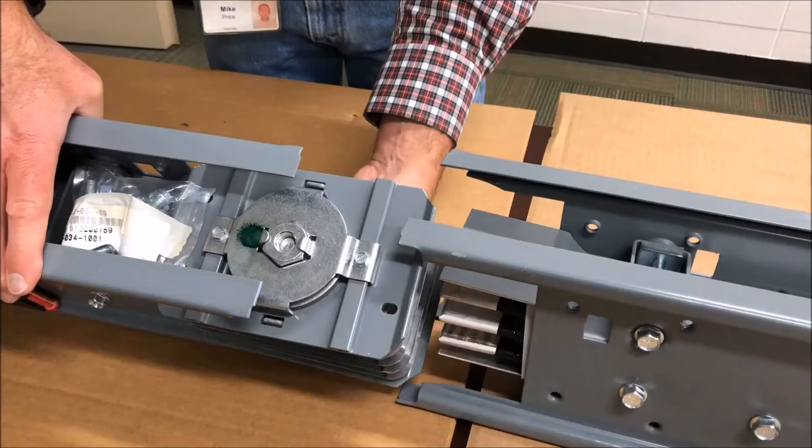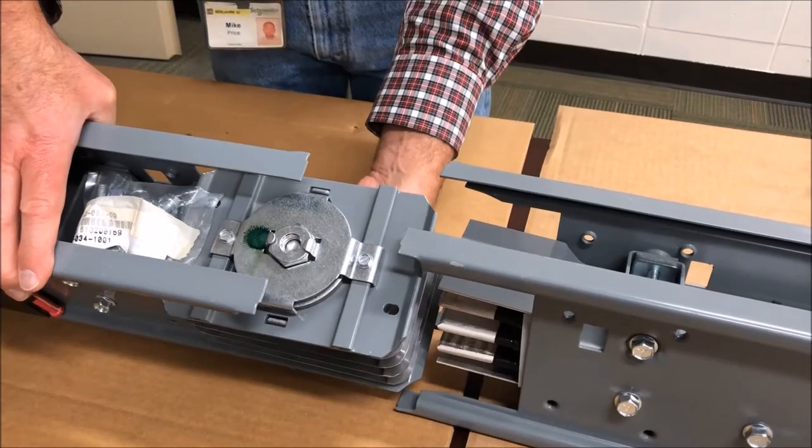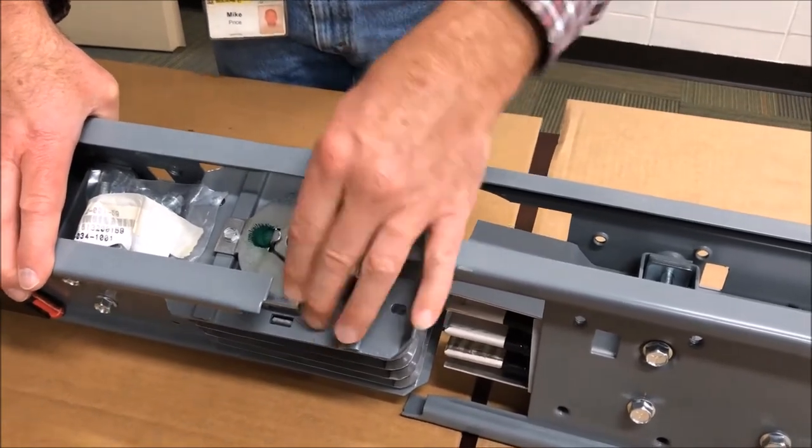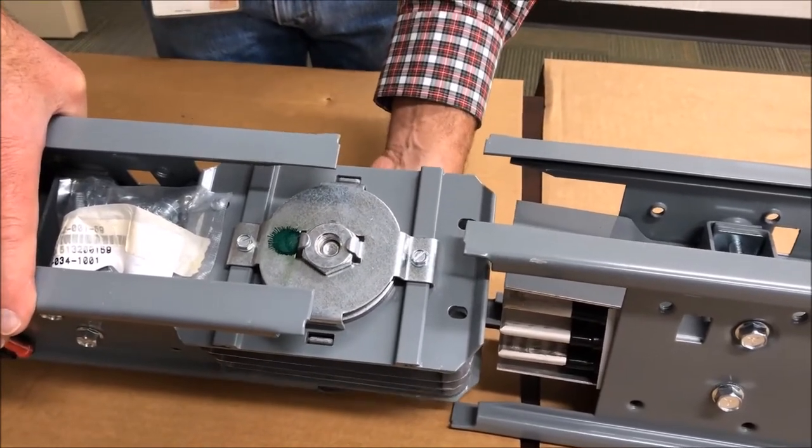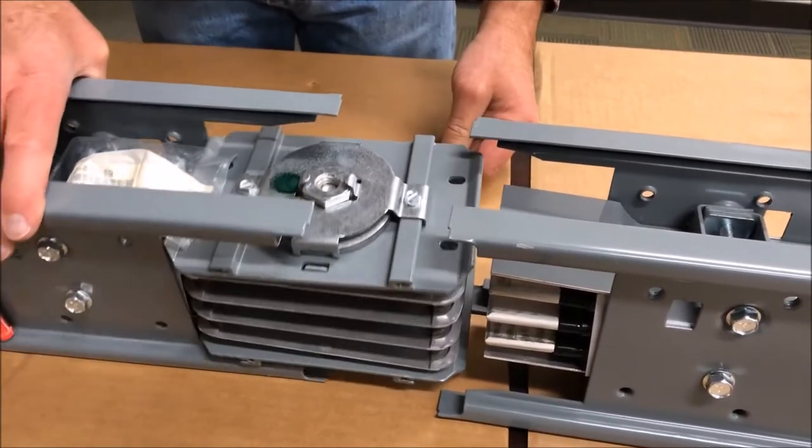Today we're going to talk about the 800 amp and above busway and how to install the joint pack assembly. First, we want to make sure the joint bolt is backed out far enough so the joint pack is loose, but not all the way out that it comes apart. This will help you slide the two busway pieces together.